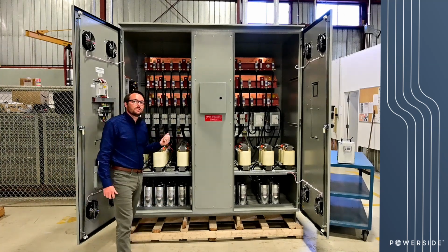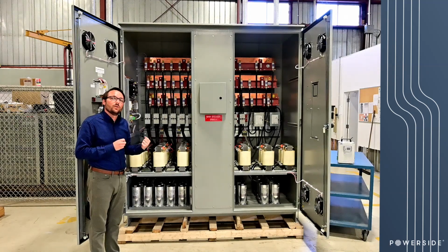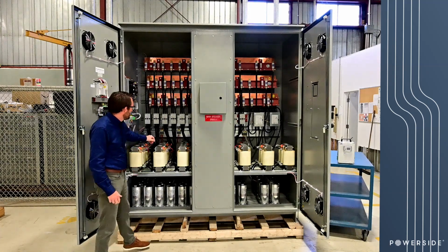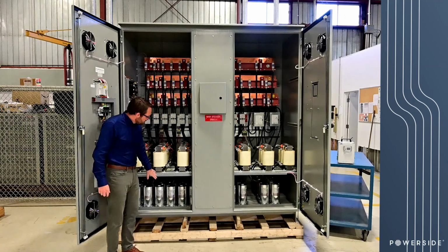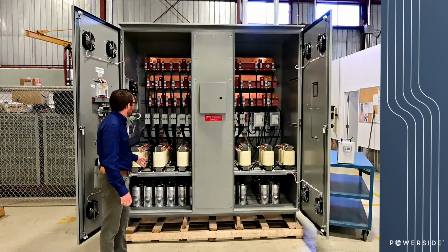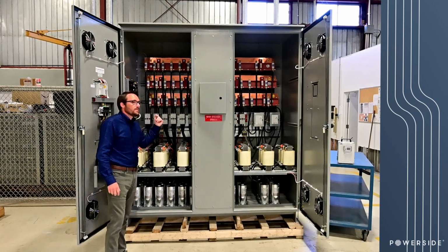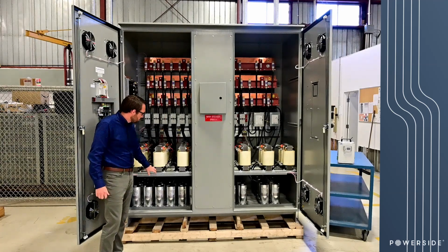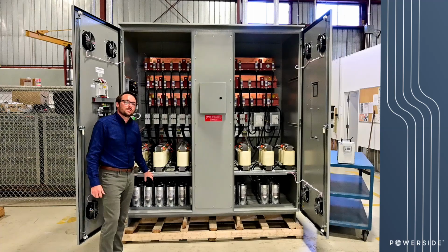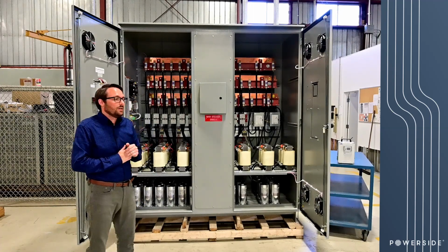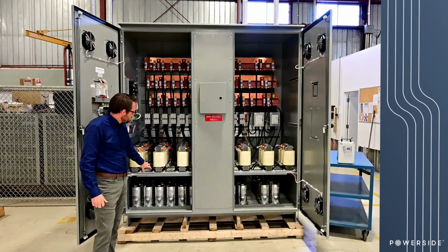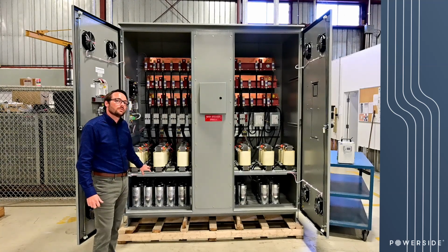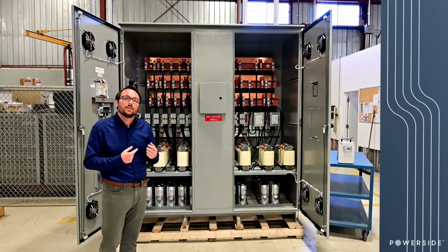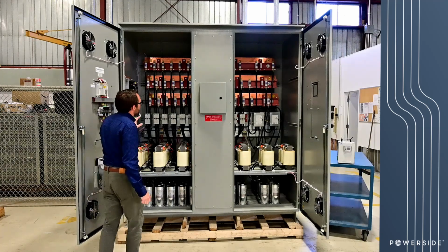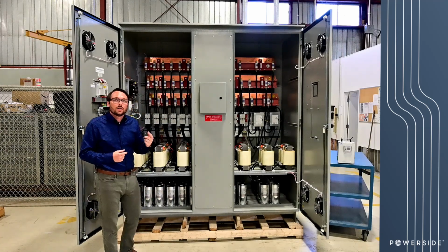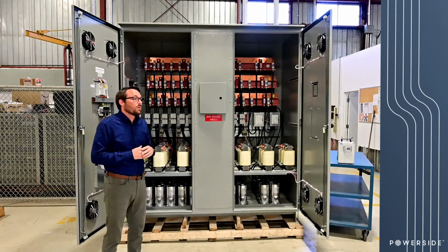The way a contactor operates is it uses the coil to close, and it closes all 3 phases simultaneously. So when this closes, current flows through the reactor down to our capacitor cells, and then when it opens, it gets a signal, it opens, and we have residual voltage in our capacitor cells. Per IEEE standards, we need to make sure that voltage discharges below 50 volts within 60 seconds before we can cycle that stage back on. So you're very limited with contactor switch systems to turn on and off stages rapidly or quickly.